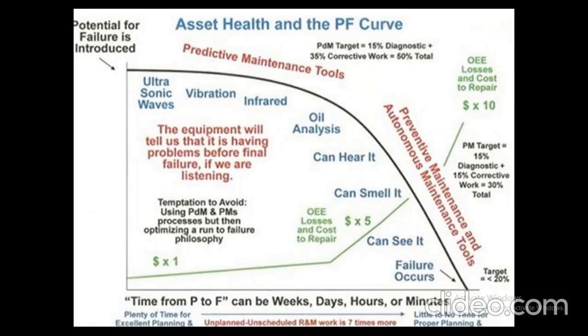So vibration has to be measured on 3 axes by the shock pulse mode. We have to see the microns per second, or the acceleration due to gravity, on X, Y, Z of the motors, especially in the textile mill, especially on the ring frames. This has not entered the mill. See, predictive maintenance is one thing, predictive monitoring is one thing. Predictive monitoring only if it is done, only then can predictive maintenance be done.